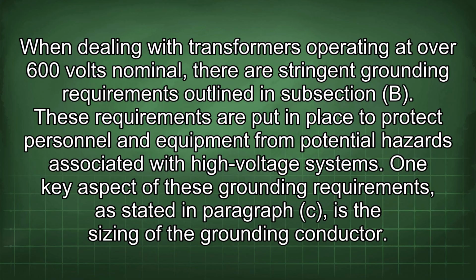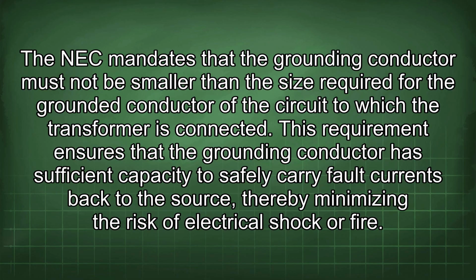systems. One key aspect of these grounding requirements, as stated in paragraph C, is the sizing of the grounding conductor. The NEC mandates that the grounding conductor must not be smaller than the size required for the grounded conductor of the circuit to which the transformer is connected. This requirement ensures that the grounding conductor has sufficient capacity to safely carry fault currents back to the source, thereby minimizing the risk of electrical shock or fire.